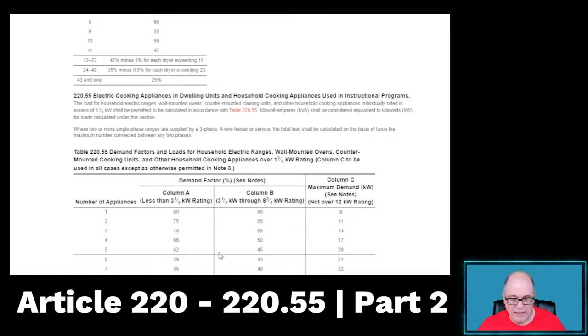Okay. So let's go back and look and see what we've got in our presentation. All right. So again, this one says 3 kW. Oh, we got to go back. Let's go back to the code. We got to see because I think this one's going to actually be under A. Let's go back, see if we're in the code book. Yeah. Look at the code. We are less than 3.5. We are under column A, and we're under column B, just like what it said in our presentation. Sweet. What is the multiplier? Well, one appliance, 80%. Column B, one appliance, 80%.